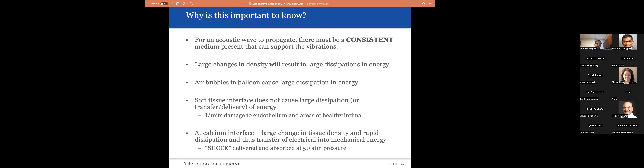So at the soft tissue interface, because there's not a dramatic change in density between soft tissue and the air and the contrast media in the balloon, it does not cause a large dissipation or transfer of that sort of shockwave per se. So it limits damage to endothelium and areas of healthy intima, and in theory the device won't promote intimal hyperplasia in areas of healthy tissue, and it's really going to focus its treatment on the plaque that you're trying to modify.